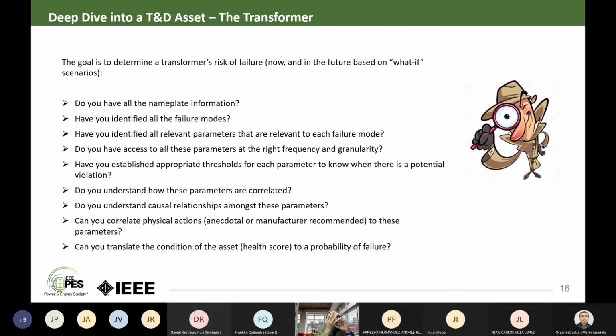Next, I need to understand for that particular transformer, what are the different failure modes? How does a transformer fail? Does it fail because of a dielectric problem? Does it fail because of a short circuit problem? Does it fail because of an accessory problem? For example, the fans failed and so the transformer overheated. So we need to understand the different ways in which the asset can fail.